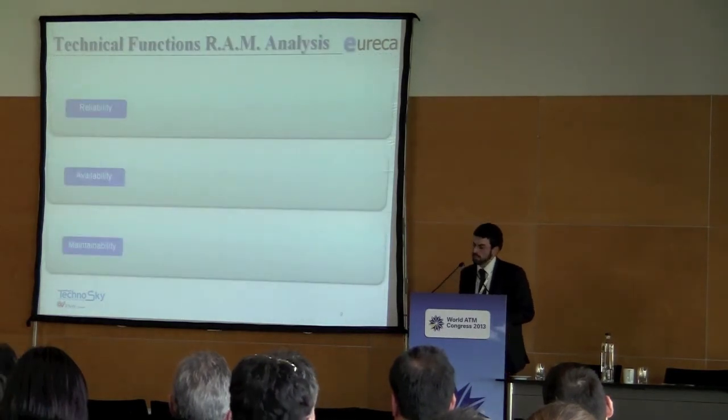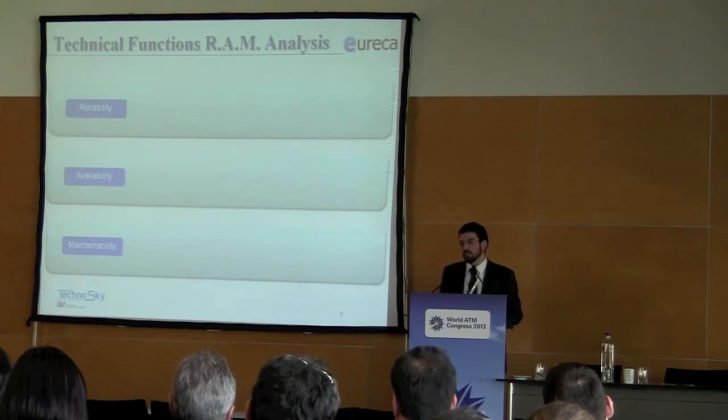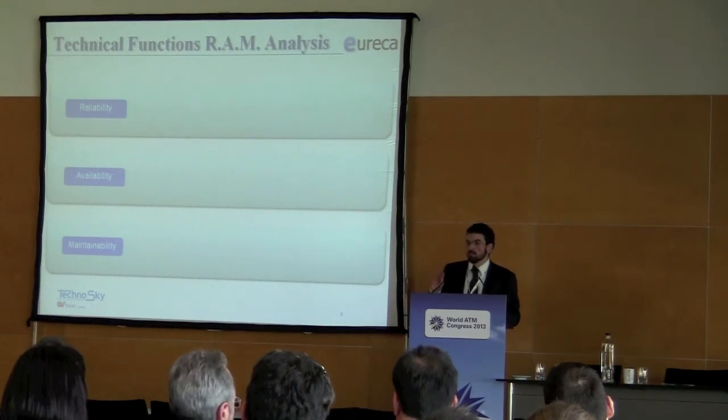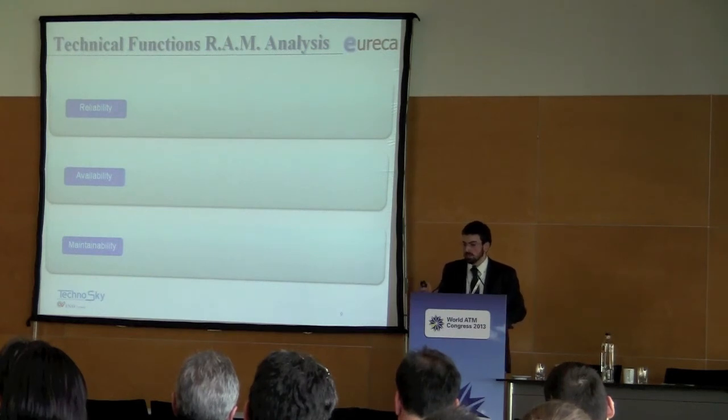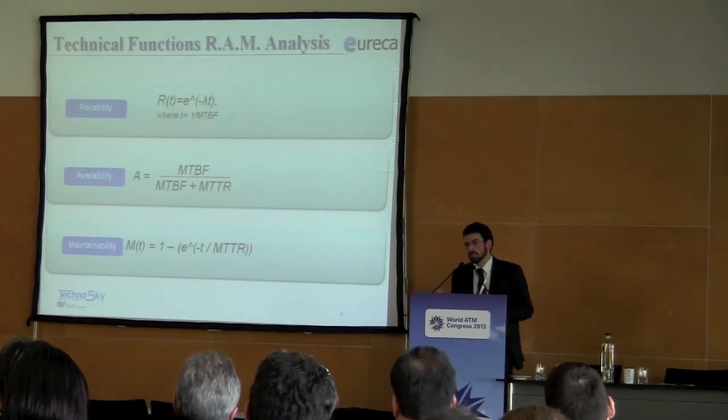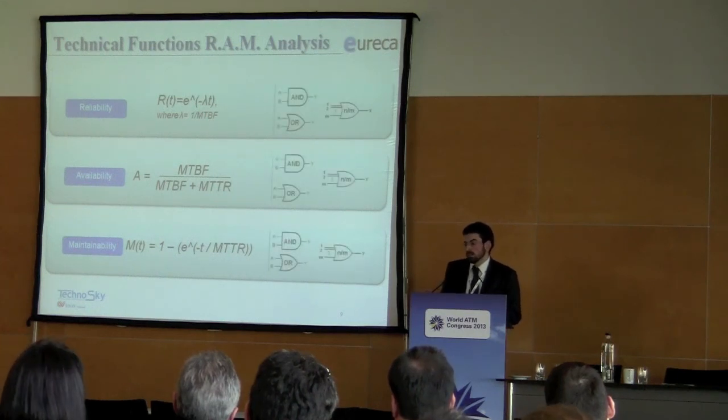So, I say that we need the MTTR and MTBF of the equipment. Through the functional tree, we can calculate these parameters also for each node of the tree. In other words, we can perform the RAM analysis on the equipment, on the root of the tree, and also in the middle layer. And this is the RAM analysis, that is reliability, availability, and maintainability. These are the formulas. Of course, we have to perform a quantitative assessment. Okay, we need a quantitative control of the air navigation services.